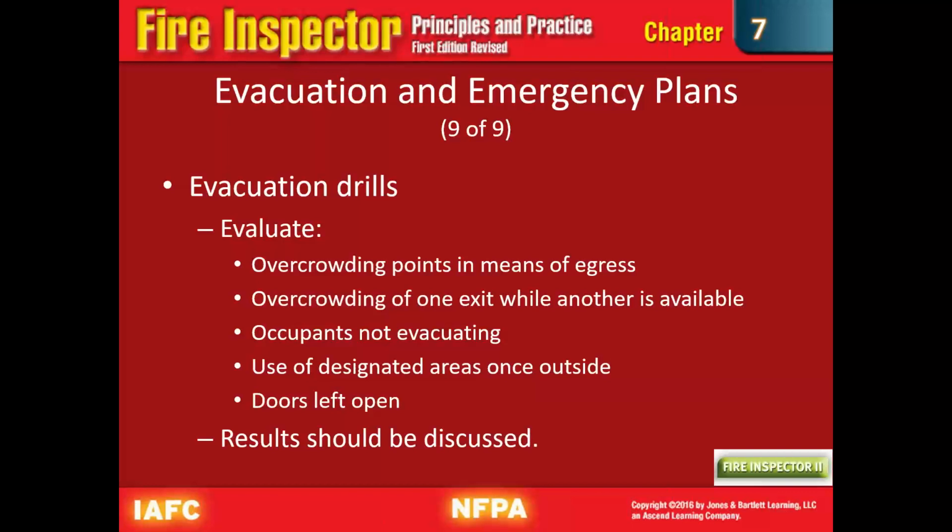In the evacuation drills, we're going to look for overcrowding points. If you have the opportunity to assess a fire drill, do it. You learn a lot. You learn of things that work, things that don't work, and you can help be that advice to help improve a drill that may save somebody's life one day. You may address some issues like overcrowding in one exit whenever there's another one that's completely open.